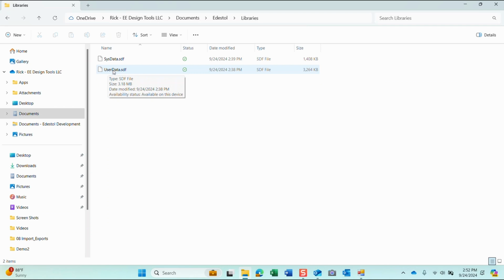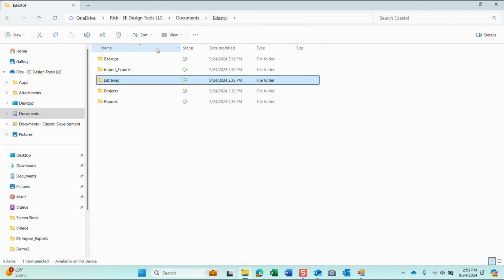I'll show how you can get in there and modify this. It contains information that's related to things that might change: breaker sizes, bus sizes. There's cable dimension information in there. There's adjustable speed drive information. There's system voltages in there, and this is also where your report configurations exist. So we'll look at this in quite a bit of detail down the road, but I just wanted to go through this file structure. And then we have a project subdirectory.